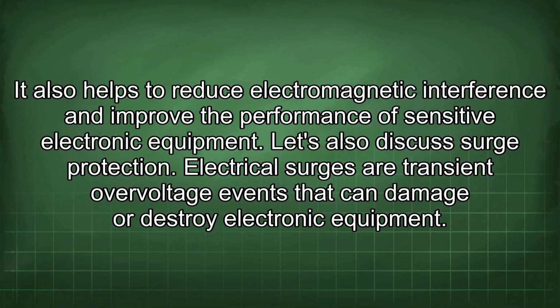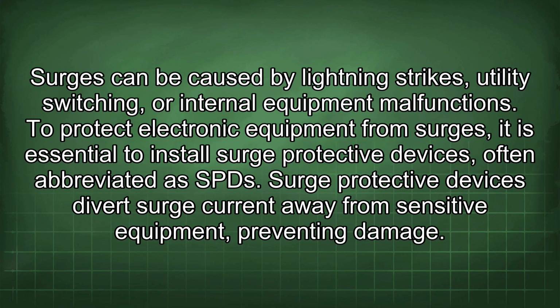Let's also discuss surge protection. Electrical surges are transient overvoltage events that can damage or destroy electronic equipment. Surges can be caused by lightning strikes, utility switching, or internal equipment malfunctions. To protect electronic equipment from surges, it is essential to install surge protective devices, often abbreviated as SPD. Surge protective devices divert surge current away from sensitive equipment, preventing damage.